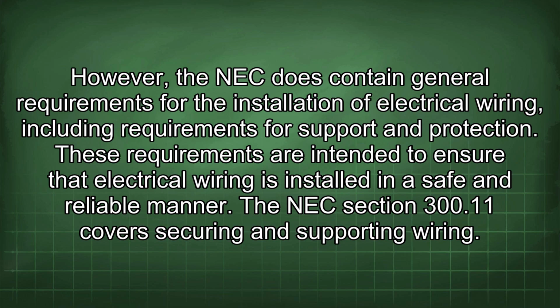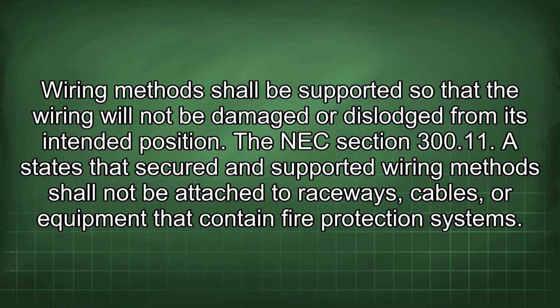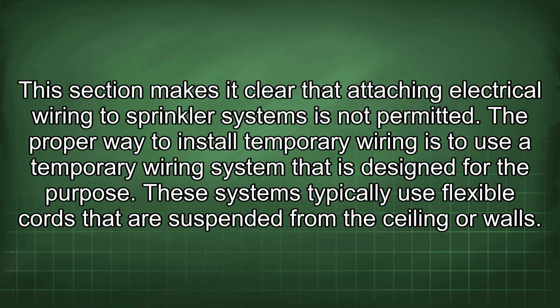The NEC Section 300.11 covers securing and supporting wiring. Wiring methods shall be supported so that the wiring will not be damaged or dislodged from its intended position. The NEC Section 300.11 states that secured and supported wiring methods shall not be attached to raceways, cables, or equipment that contain fire protection systems. This section makes it clear that attaching electrical wiring to sprinkler systems is not permitted.